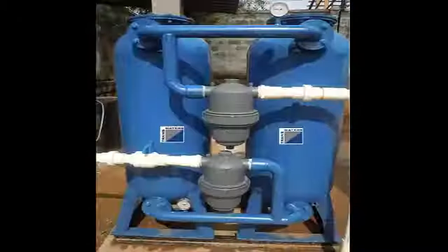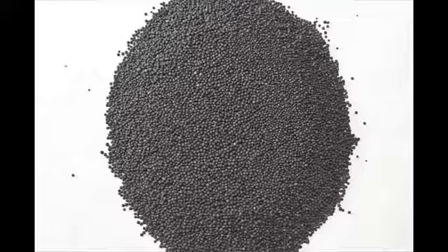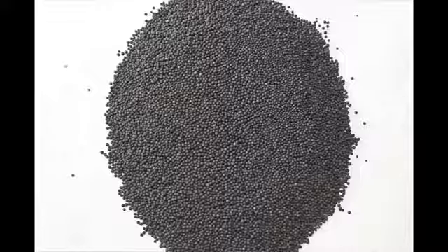If you only have two cylinders, one could be a multi-grade filter and the other a softener. People mix sand and carbon in the first cylinder, putting them stage by stage based on the grading, and the second one can be the softener. If you have iron, then people have an additional cylinder to remove dissolved iron from the water, using different manganese dioxide based material. So if you live in an apartment complex, you have multiple stage cylinders.